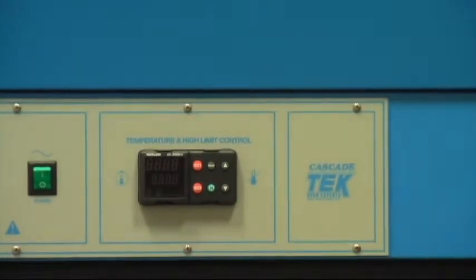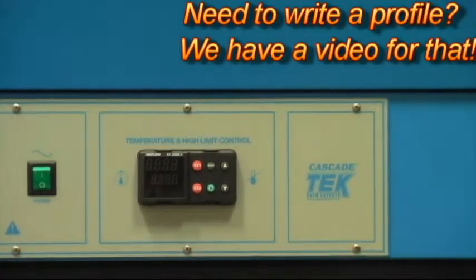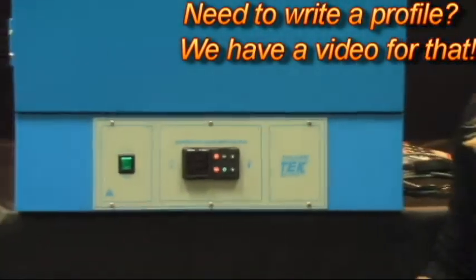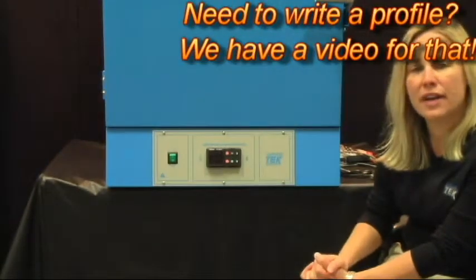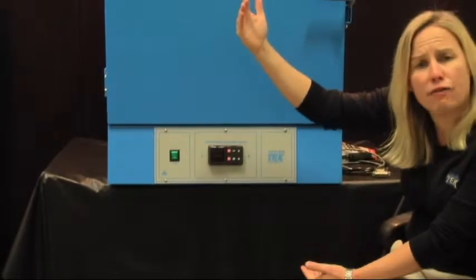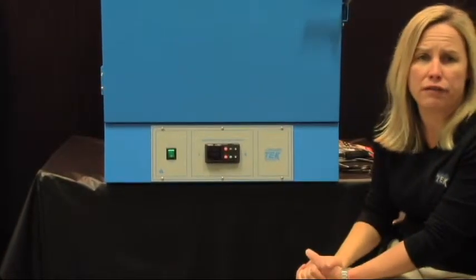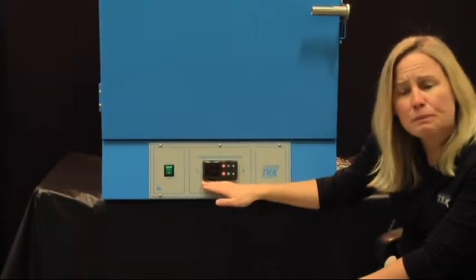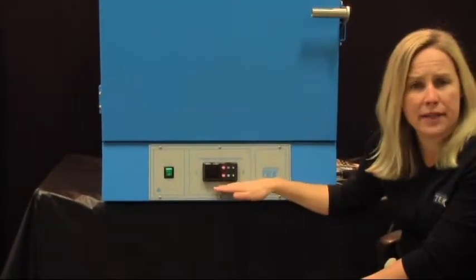So, for example, I want to start at ambient room temperature. I want the oven to go up to 100 degrees C. I'd like to stay there for four hours. And then at four hours, I'd like to go to 150 degrees C. And then at the end of that four hours, I'd like the oven to turn off. This controller is capable of doing that automatically for you if you program it.